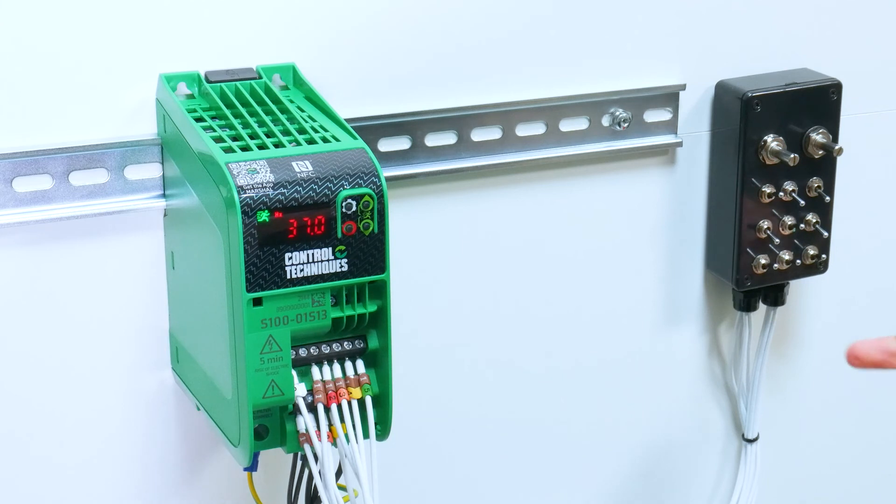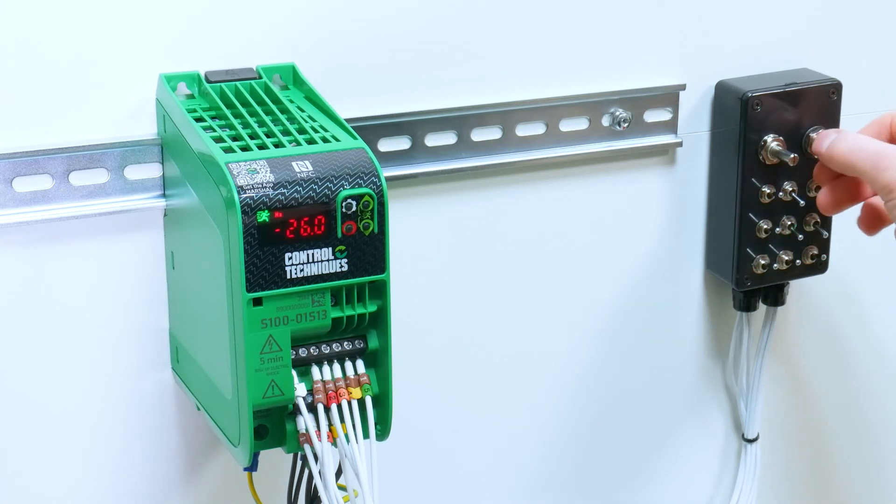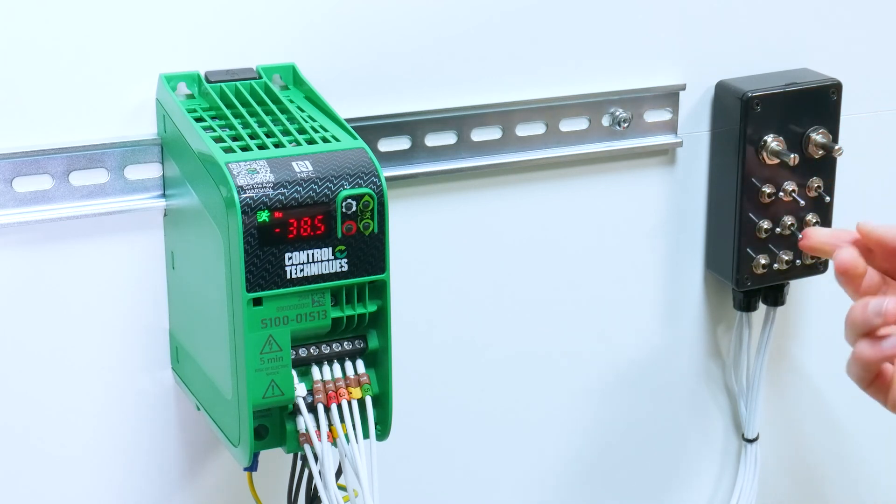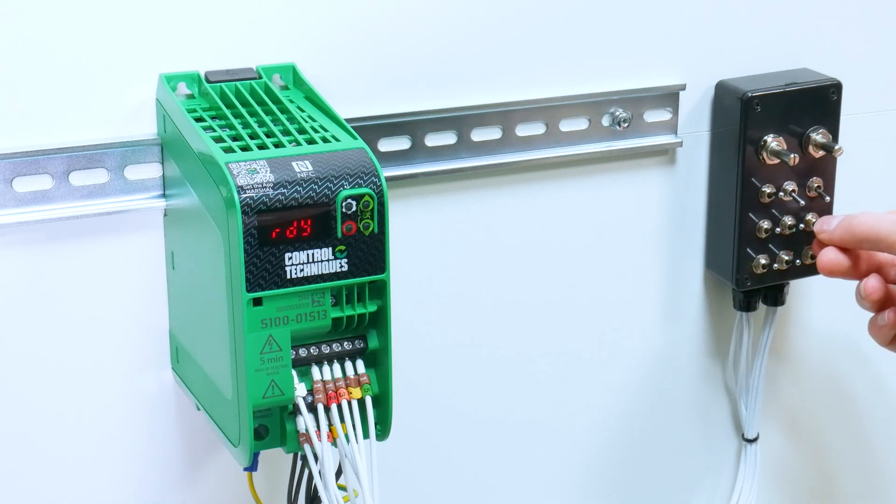I can then remove the run forward signal and engage the run reverse, and the motor will run in reverse. Removing the run reverse, the display will show decel until it stops. Then removing the enable, I'll go back to the inhibit state.